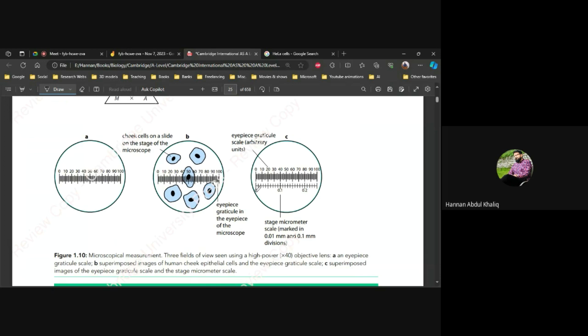And obviously, if it's 0.1, then with 10 readings within, how much would each be? Every reading would be one small scale. Okay, sorry, let me correct it. One small scale equals 0.01, and the larger one equals 0.1, and its readings go up to 0.25. You can confirm it from the book over here. This is the last reading, and we need to calibrate. The proper word would be calibrate. We need to calibrate which one? The eyepiece reticule to this scale. This scale is called the stage micrometer.